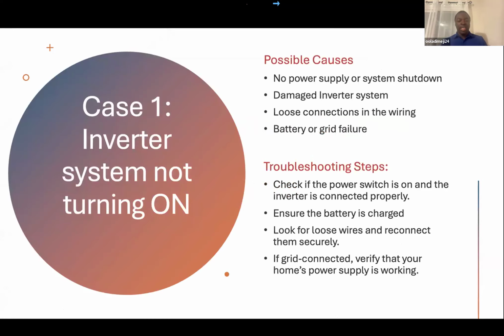The case one we're looking at is the inverter system not turning on. Possible causes: you are not getting power supply, your system is shutting down, a damaged inverter system, loose connections in the wiring, battery or grid failure. You can see that these are individual components of what we've talked about as regards components or devices in a whole system. How do you troubleshoot this?